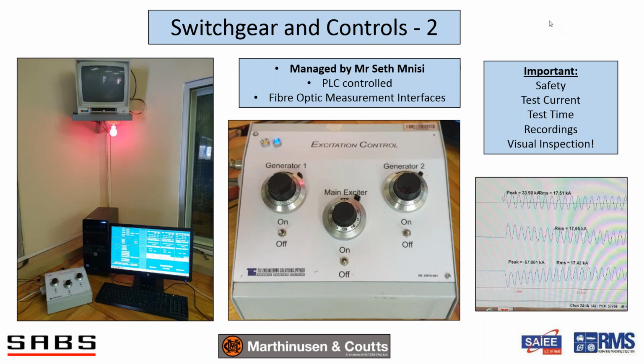Then recordings are important. So here's a recording of the first fault current that we did on the 31st of August. It's quite interesting. I'll tell you about that later, what actually happened here. And in terms of the test, the most important aspect for a customer is actually a visual inspection after the fault, or a video recording. The visual inspection is what you check for. How did my equipment get damaged? Did it manage the fault, etc.